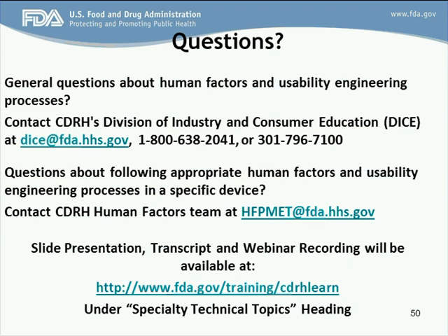And I think some of that is also coming from looking at post-market signal data of your predicate device and similar devices on the market. What we have learned from the market and use of those devices so far: does it introduce any serious harm issues to the patient or user? So looking at the post-market signal may also help you determine whether there is serious harm to the patient or user.